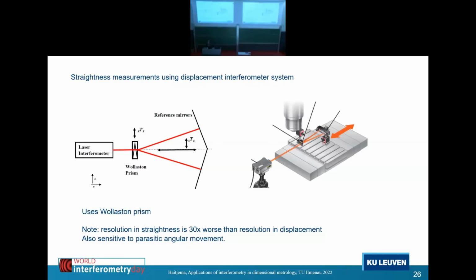You see it everywhere. I must tell you a small warning. The resolution in the straightness deviation is much worse than the resolution in the displacement. It's about 30 times worse. You have also a long-range option, and it's 300 times worse. So in fact, and you have a parasitic, if this angle changes a little bit, you have also a parasitic movement. So in the end, I don't think it's a very fantastic method, but okay, it's in the box that people use.